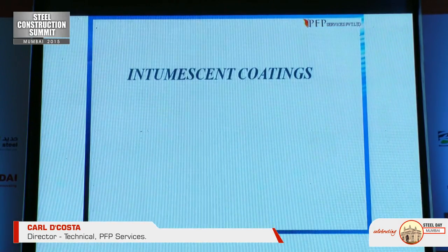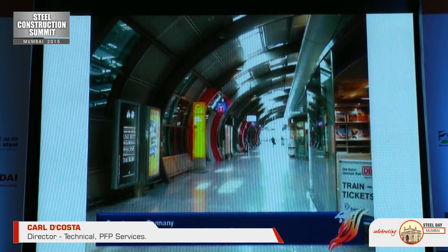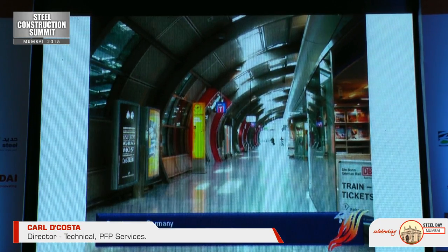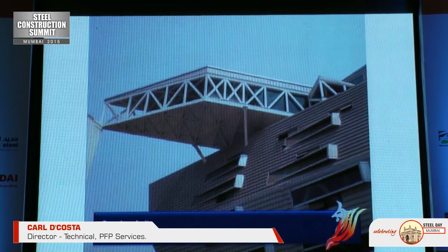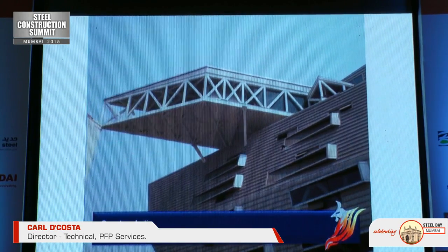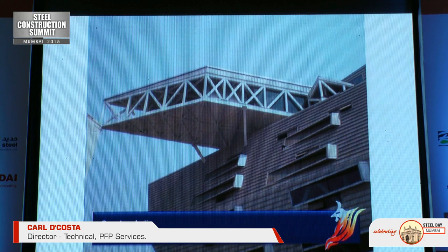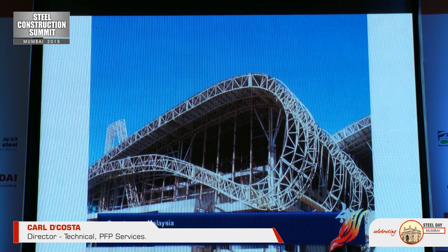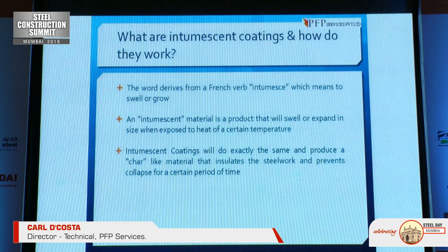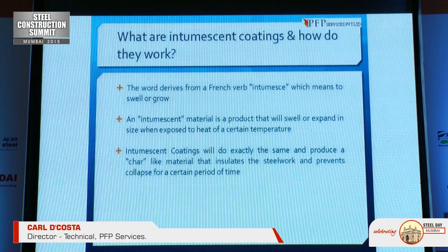The next is intumescent coatings — used in internal railway stations, commercial showrooms, and international airports. The word derives from the French verb 'intumesce,' which means to swell or grow. An intumescent material is a product that swells or expands in size when exposed to heat of a certain temperature. Intumescent coatings produce a char-like material that insulates the steelwork and prevents collapse for a certain period of time.